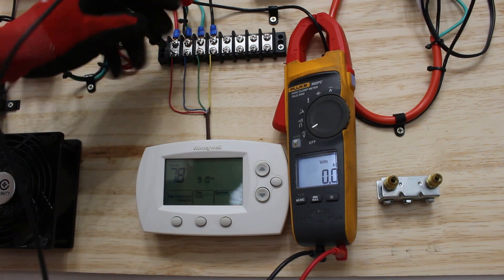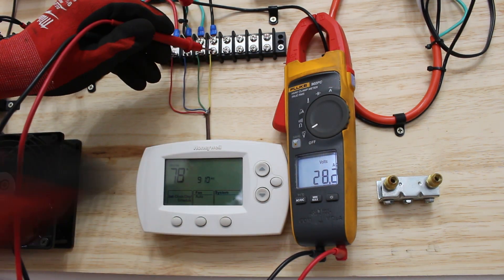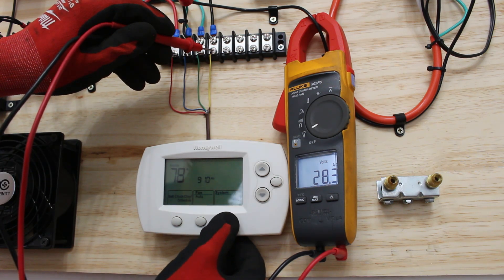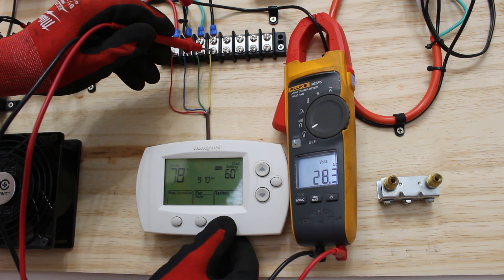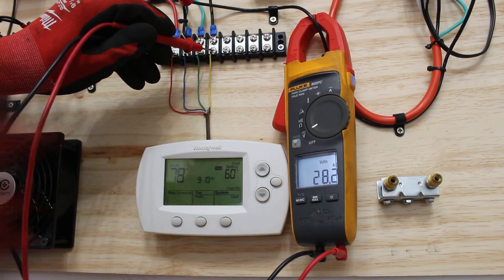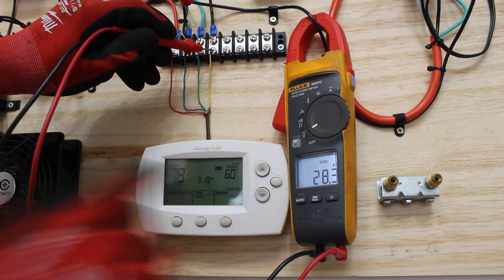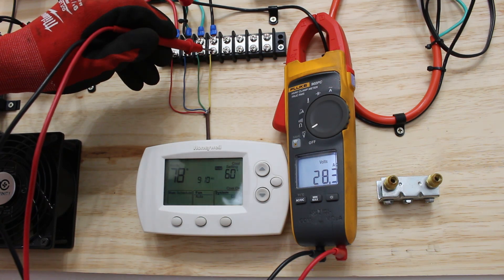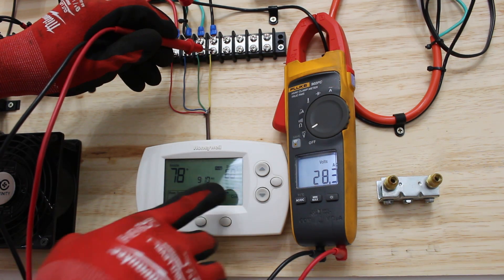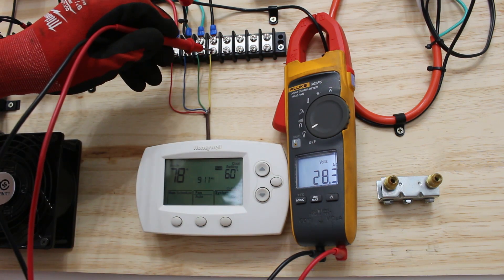When we set the thermostat to cooling, Y will close with R and G will close. So let's go ahead and put the system on cooling. We already know what happens with G so I'm going to show you what happens with Y because that is our cooling wire. Right now we have 28 volts, circuit is open. We're going to set it to cooling. Set the temperature below the room temperature and watch the voltage. Right there, there is a cool on blinking, that means that there is an internal time delay built into the thermostat. So once the cool on goes steady and our time delay passes we're going to see a voltage drop.